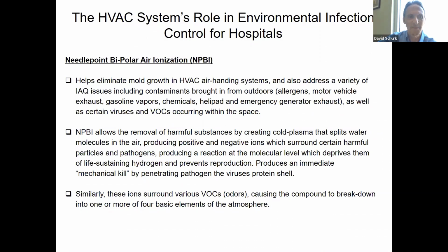The beauty of this product is this: it can do what UVGI does in terms of helping keep air handling surfaces internally clean of biological growth like mold and mildew on cooling coils. But it can also agglomerate particles in the space. The ions extend into the space through the ductwork and agglomerate small particles through electrical attraction. These ions are both positive and negative in charge, and when they contact an oppositely charged particle in the space, they attract it, and attract others. Those particles then become bigger and easier to move from the space, and easier for the filters to pull out of the airstream.